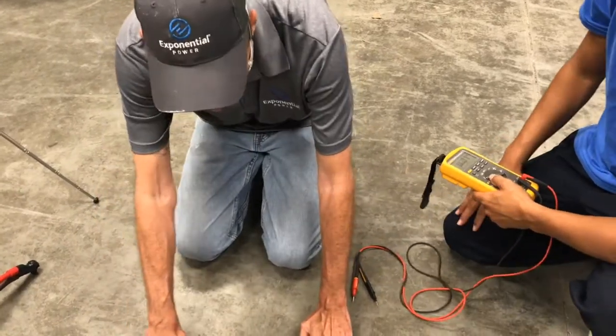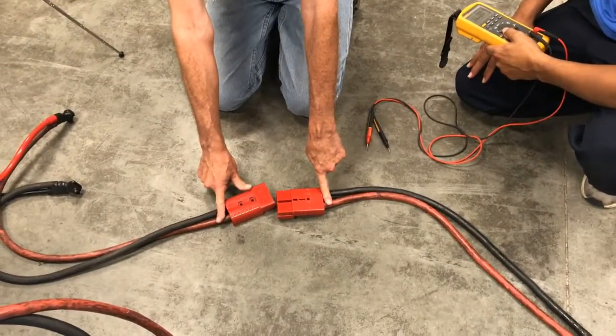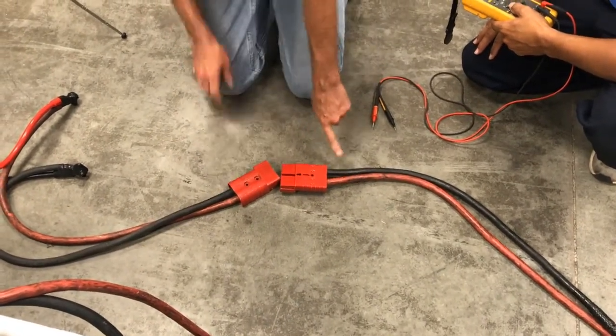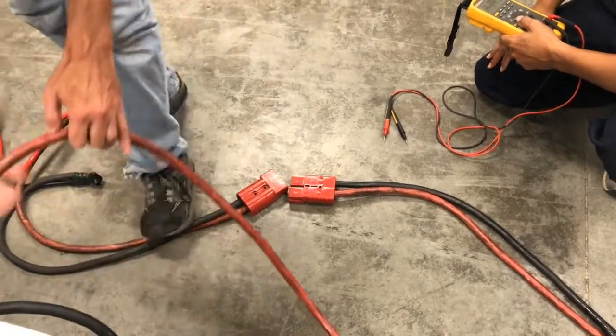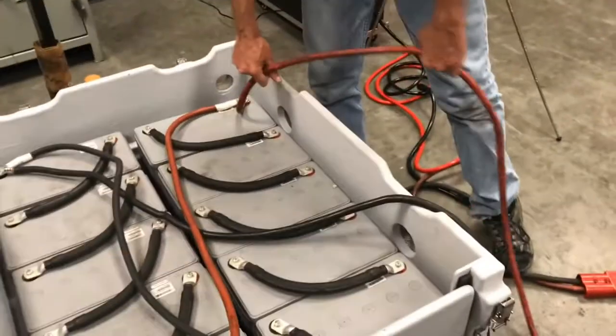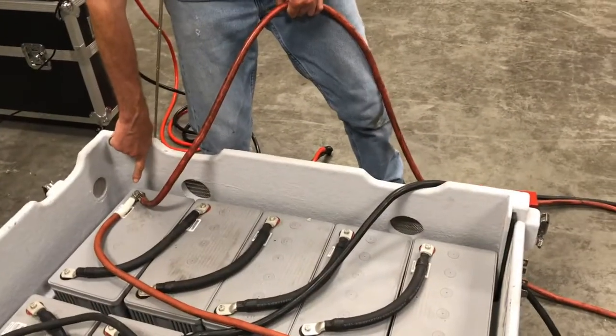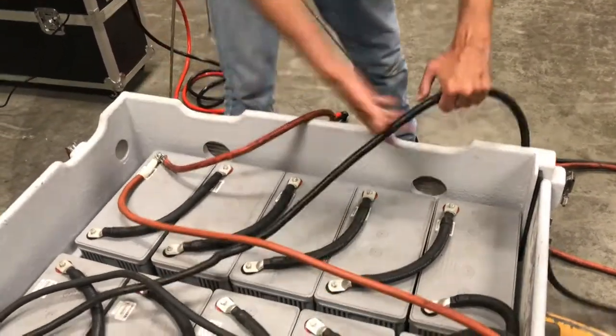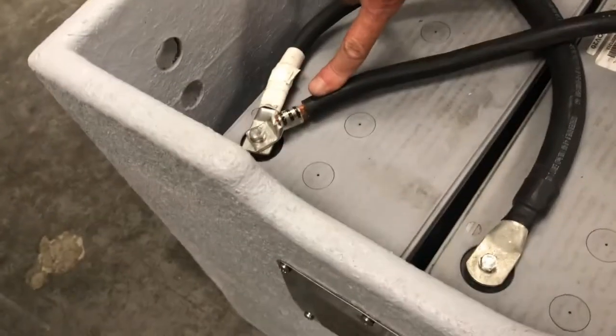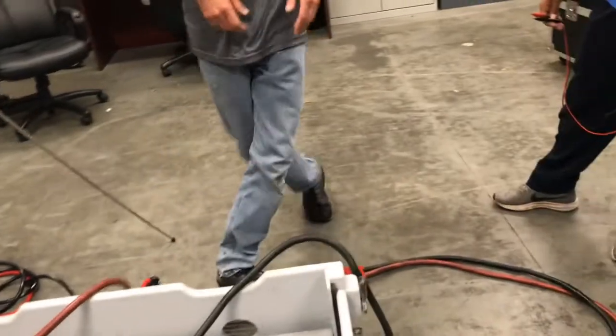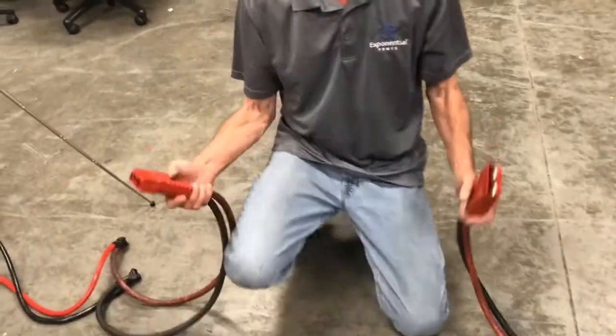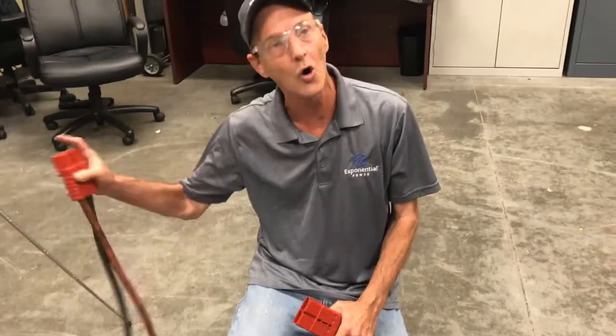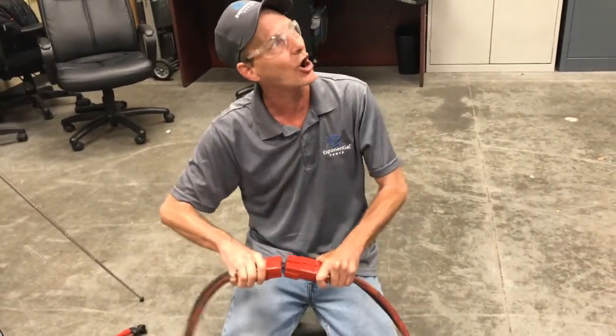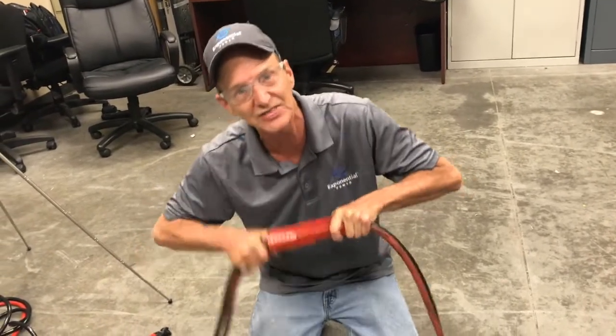When I connect the Anderson connector together, I want to verify cable colors. Red is positive, black is negative. They're marked on the Anderson connectors, but I also want to go back to the other end of the cables and verify my red cable actually lands on the main positive terminal of the battery. My black cable actually lands on the main negative terminal of the battery. So that way when I connect this connector together, I know that my polarities are correct. There's no load, no power here. I'm not going to get an arc or have a problem when I make that Anderson connector to connect to the load bank.